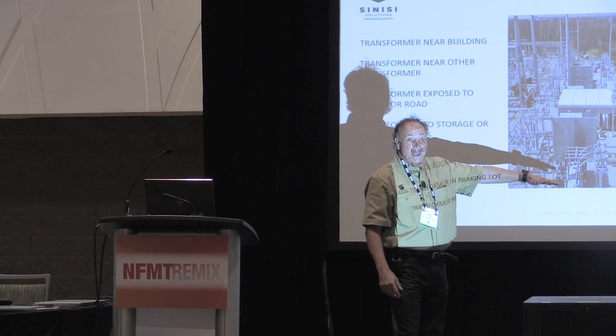It's about people, places, and things, including wiring and cabling. We've worked with municipalities on this. If you're in a municipality where one substation provides power to your facility, say you run a long-term care facility with just one transformer for the whole community, go to your power company and ask how they're protecting you and what resilience they provide. You can have all the backup power you want on site, but you still need that substation. Your generator only lasts so long, and you're on limited lighting, fire protection, and alarm systems once it fails. There's a lot that goes into that. So if you go to your utility and say you're paying the bill and they're supposed to be in compliance, they'll often pay for the fire barrier.